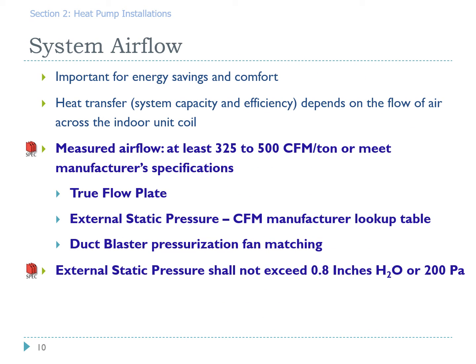Another specification is around system airflow. It's important for energy savings and comfort, and the heat transfer, which is really the system capacity. And the efficiency really depends on the airflow across that coil. And so the calculation for BTU output is CFM times the density of air times the temperature difference. So airflow is extremely important, indicated by the CFM. Low airflow reduces efficiency and capacity.